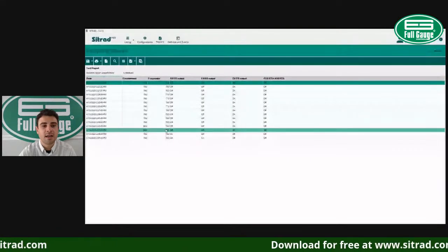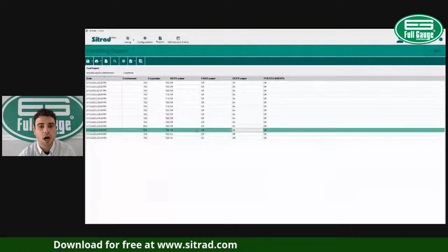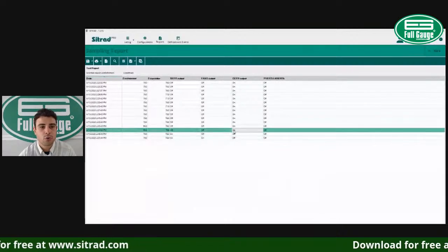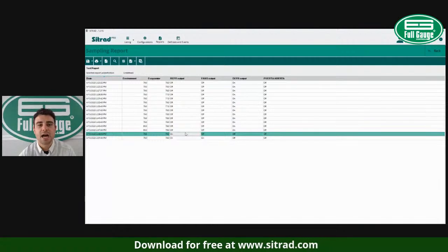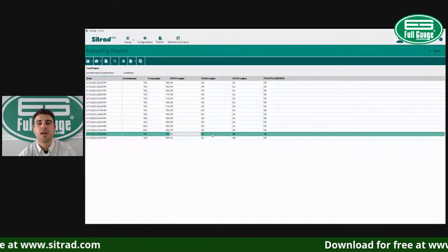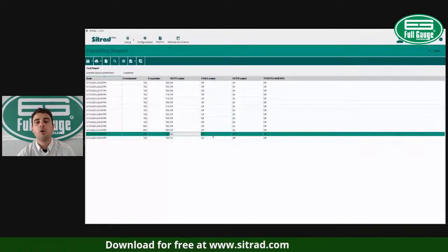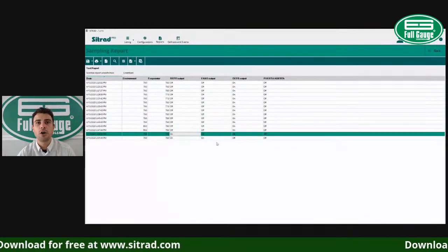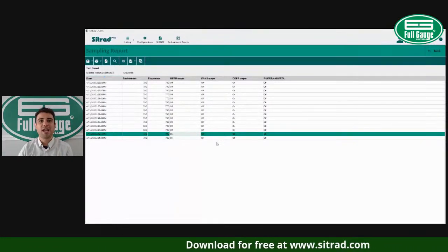And here's one interesting thing. Here you can see when the defrost went off, switch from on to off, and now my compressor is on and the fans are off. Why are the fans off in this case? Because this is a freezer application. We want to cool down the coil. We want to drop the temperature of the coil before bringing the fan on.